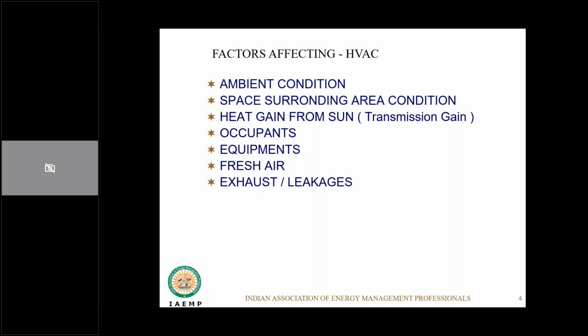This becomes very important when you're doing industrial application, specifically for pharmaceutical and semiconductor industry, where you have to be very sure that any dust generating process within the room is exhausted out so that it doesn't contaminate the other area. And all your infiltration or leakages are from a cleaner zone. It doesn't add to the room particle count. So again, the HVAC system plays a very important role in establishing these proper cascades and in maintaining exhaust and leakages.